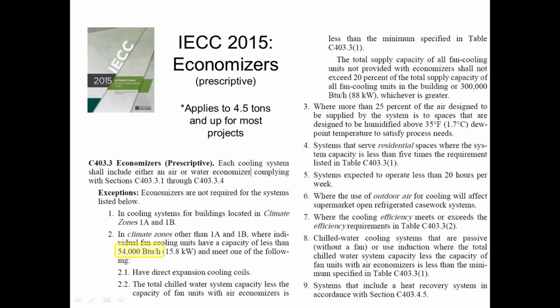So by doing this new cutoff point, it makes it more cost effective overall. There are some exceptions to it where you don't have to do the economizer. The big ones that would come up in relation to rooftop units are, if this was number 4, a residential space, then 54,000 times 5 becomes the limit. So essentially you don't have to put economizers in commercial buildings if the space it's serving is residential. Number 5 comes up a lot for a church or something.